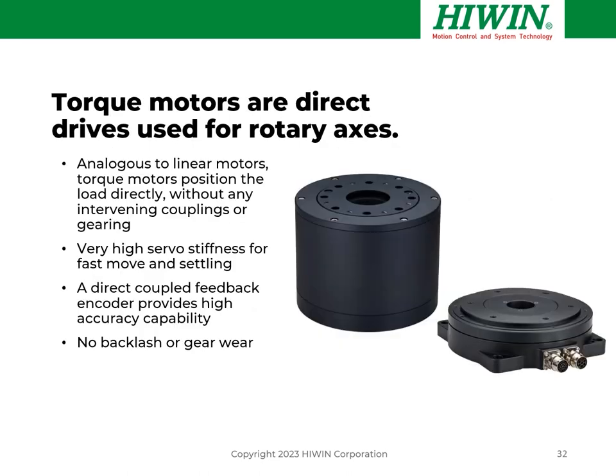What about rotation? Sometimes we need rotation rather than linear motion. Torque motors are often used in this case — a type of direct drive employed in rotary stages and rotary positioning tables. Analogous to linear motors, the torque motor positions the load directly without any intervening couplings or gearing, giving very high servo stiffness, fast moves, smooth scanning, direct-coupled feedback encoder for high-accuracy capability, no backlash or gear wear for very long life, and direct drive with direct measurement — the best possible combination.